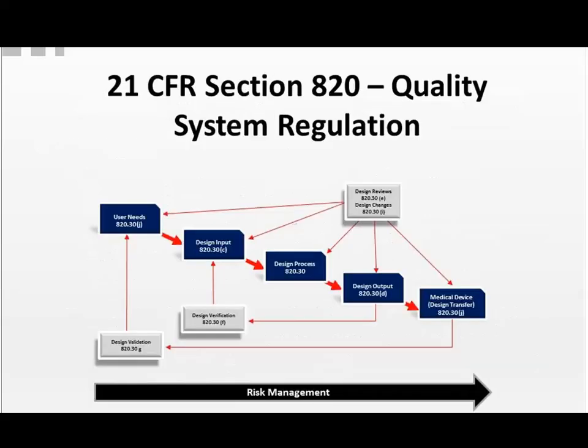Now, what you see here is the simplistic medical device design control model that's presented in the FDA's quality system regulation, which the FDA uses to assure design coverage and compliance to their regulation. Essentially, all of the global medical device regulations indicate that the manufacturer must apply the process of risk management from a device's initial conception until the device is decommissioned and disposed of. Pretty much everybody agrees with this. What we're talking about is applying risk management throughout the device's entire life cycle.